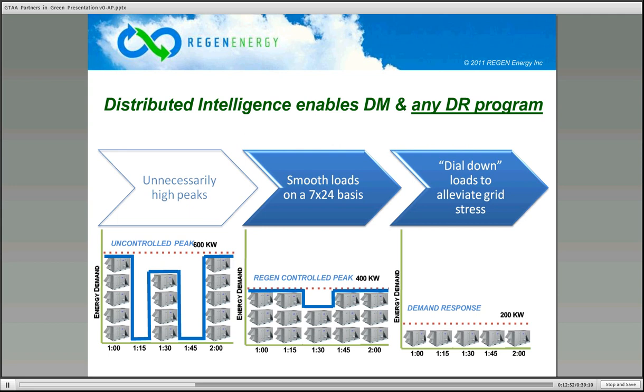Now if you participate in demand response, what we do is, remember the 83% duty cycle? Let's knock it down by 15 minutes. That takes it down to, I think, 78%. So 2.25 hours out of 3 instead of 2.5 hours out of 3. What we would do is dial down each unit by 1 or 2 notches.